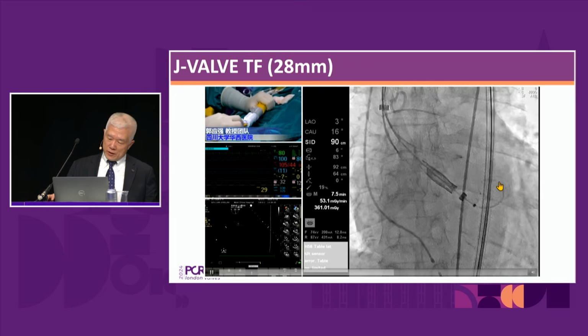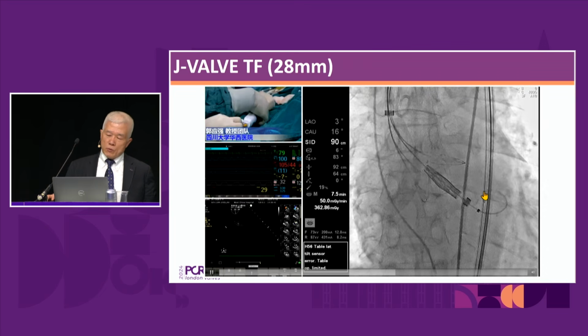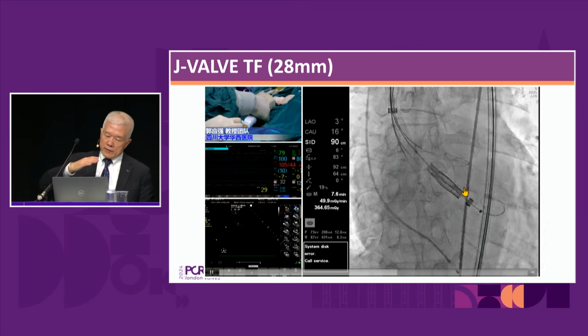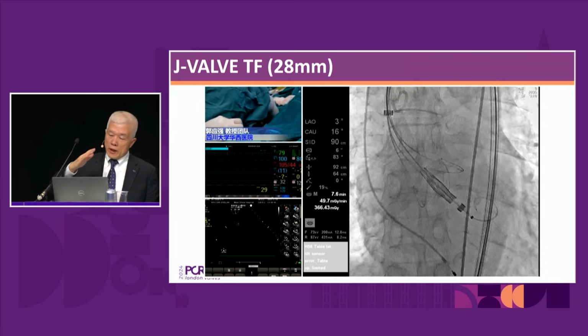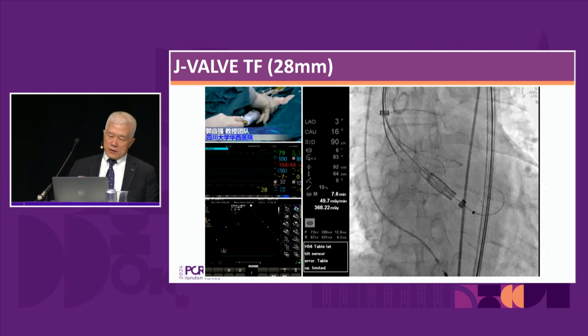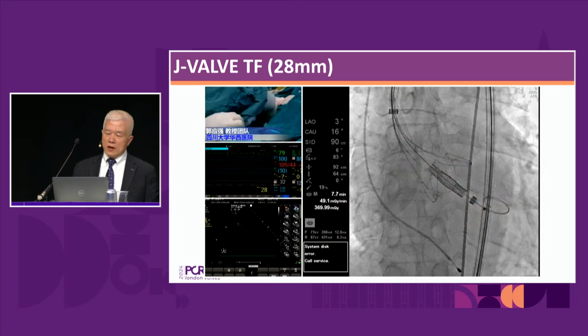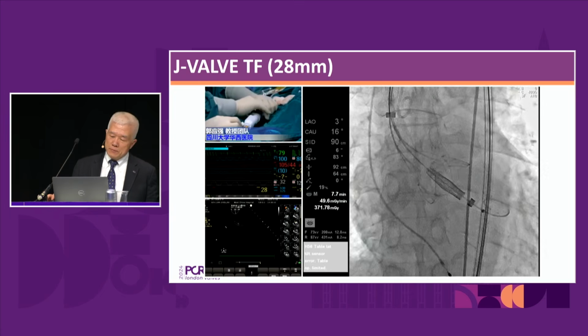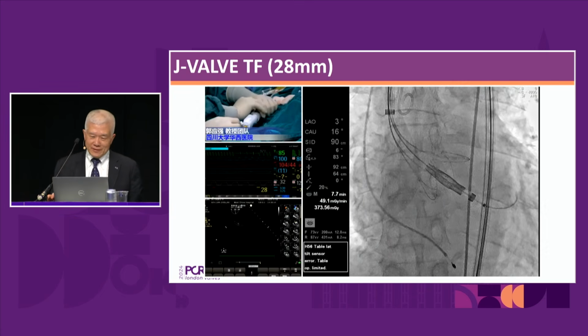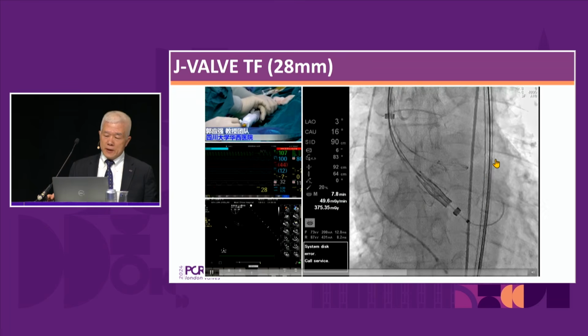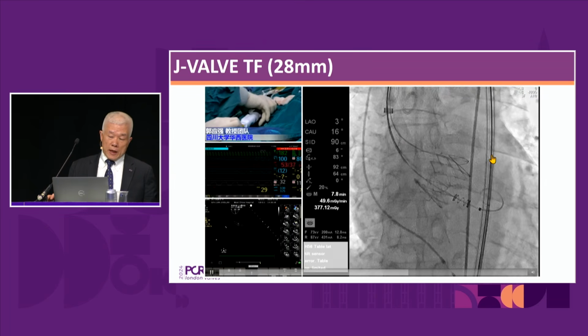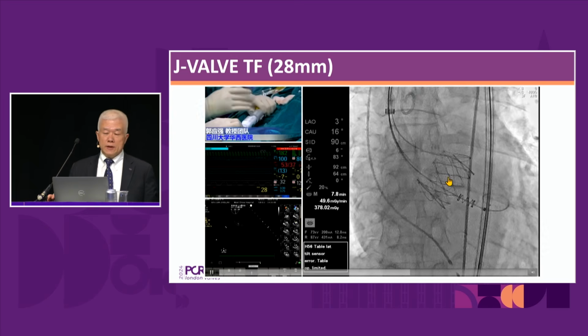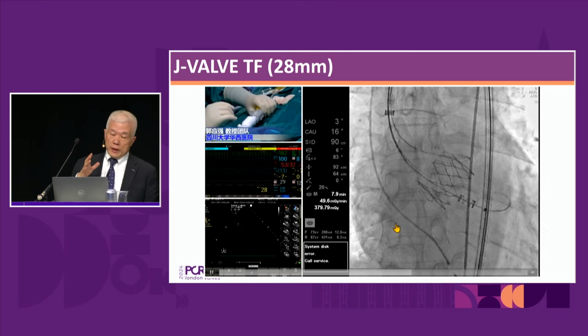You just slightly maneuver the wire. You can centralize the valve. You can see the trajectory is really good. And then just rotate the gray knob counterclockwise. It's under fast pacing, okay, because you have high pulse pressure. The valve releases, and it's a sequential release step.